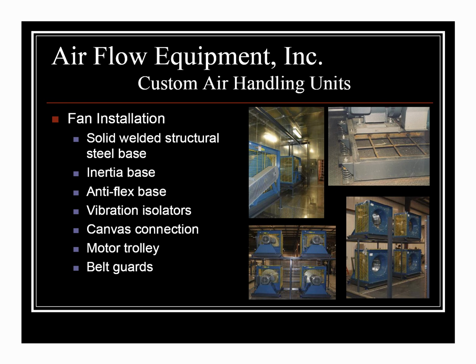A concrete inertia base is available. We can pour the concrete here in the factory, or it can be field installed—either option is available. We also make what we like to call an anti-flex base, a fan base fabricated from 8-inch by 4-inch by 1/4 inch wall tubing, offered as an alternative to a concrete inertia base. That 4-inch by 8-inch by 1/4 inch tube is very stiff and has quite a bit of mass. We've found in many cases it's as stiff or stiffer than a concrete inertia base. So if you need a very tight vibration spec but don't want the weight of concrete, we can use that 8-inch by 4-inch by 1/4 inch tubing to create a fan base that will be extremely stiff.